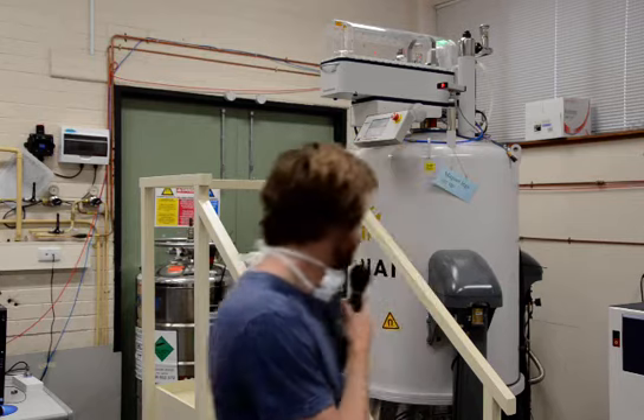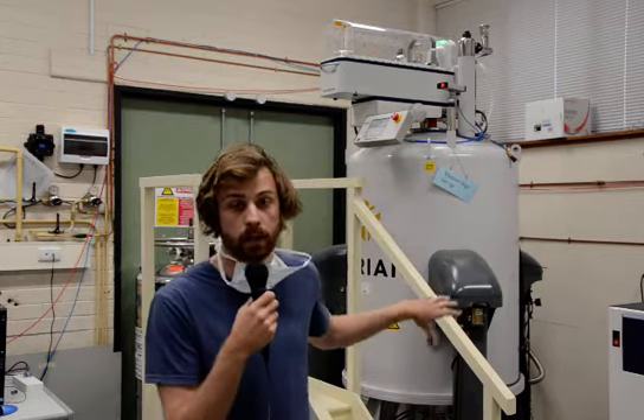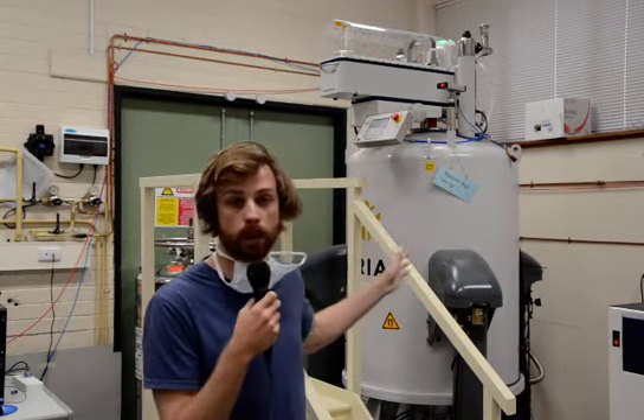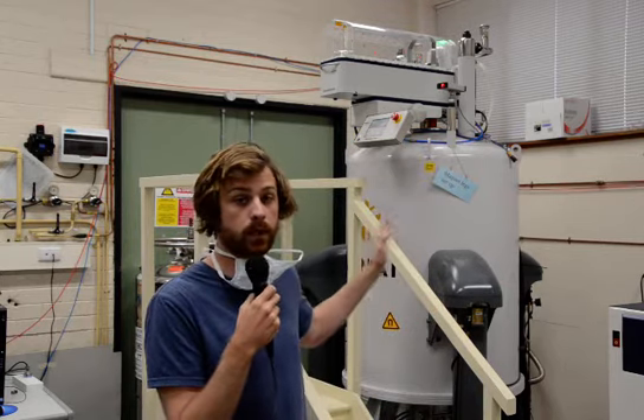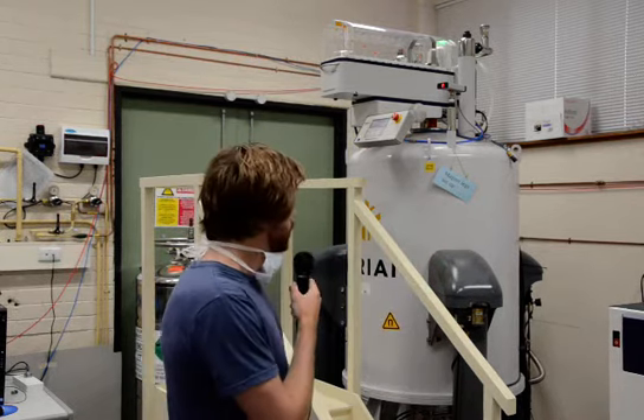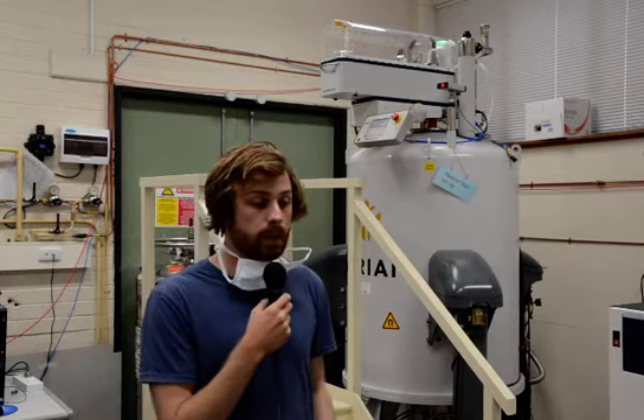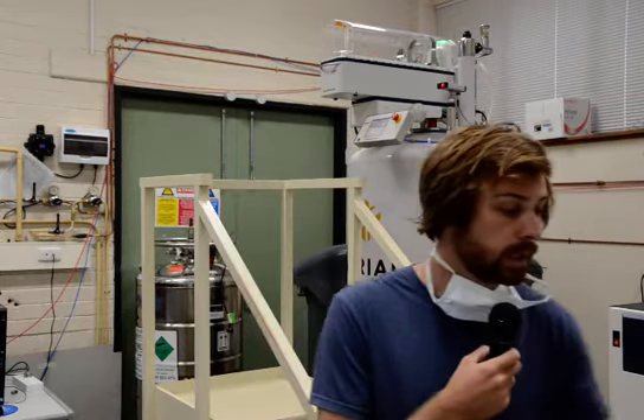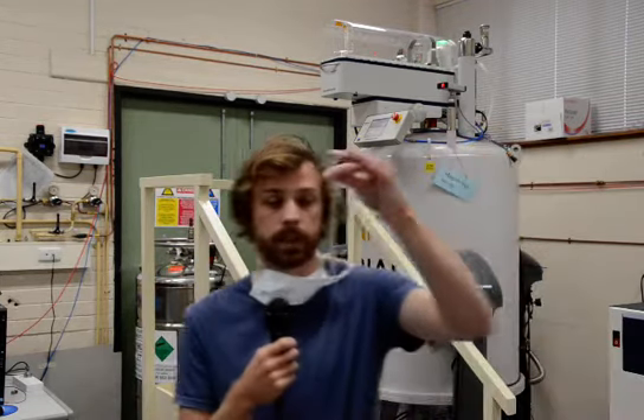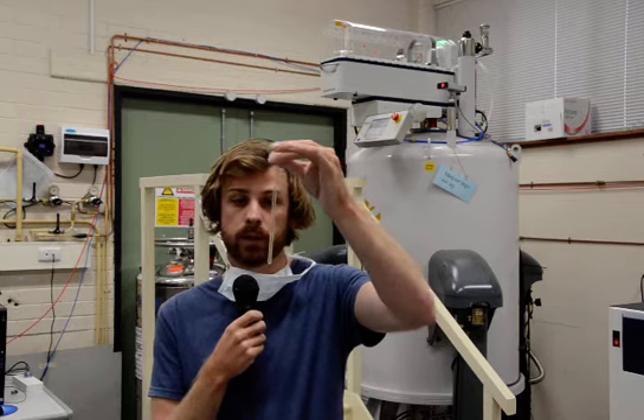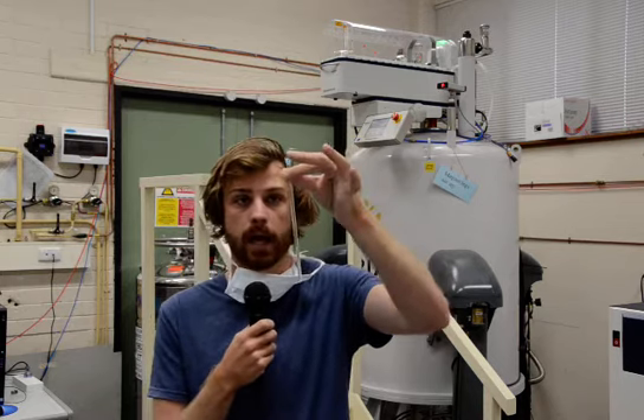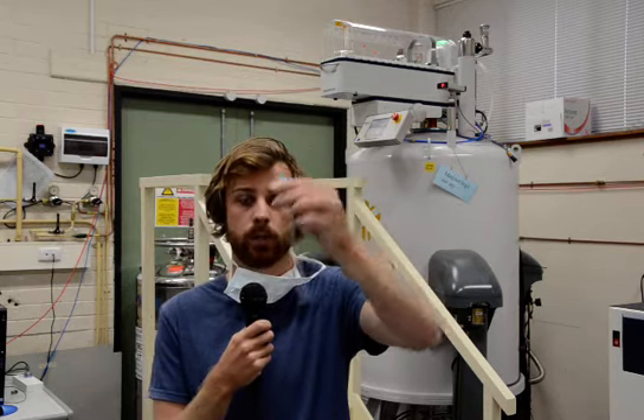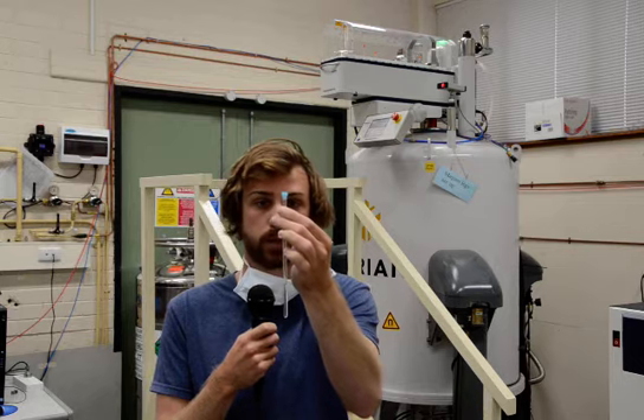So today we're going to be looking at the 500 megahertz NMR, which contains a cryoprobe, which can do much cleaner spectra than the other two spectrometers we have here, which is a 400 and an older variant as well. To set up a sample in this particular machine, what we do is we take a sample, such as this one, with some solvent, so the sample is dissolved up, and we place it in this glass tube with a sample lid on top as well.